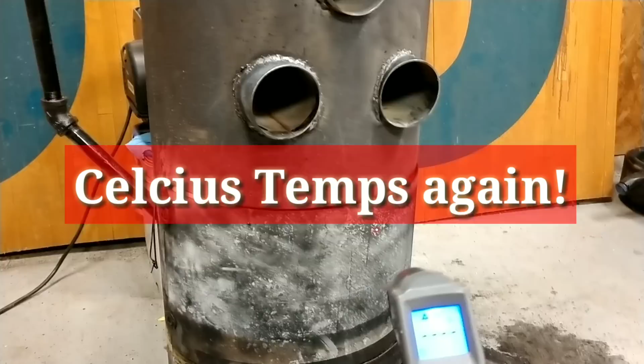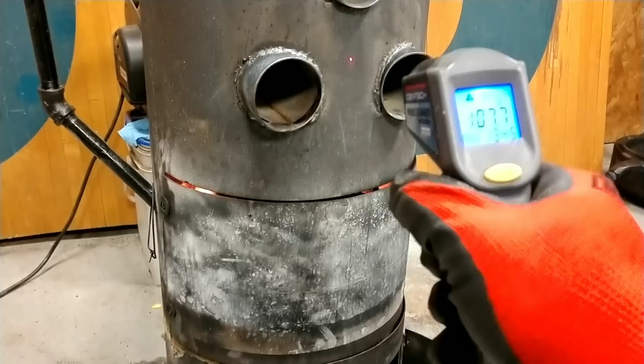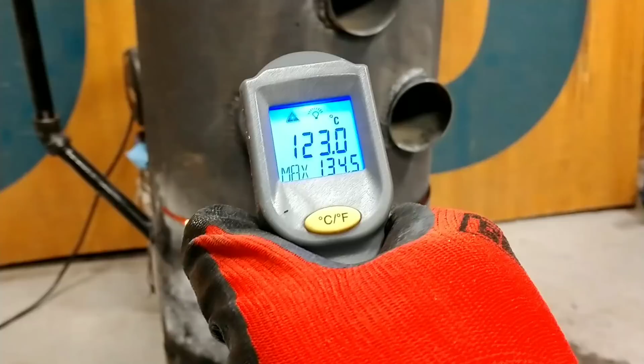And let's check some temperatures. It's been a couple of minutes now. The door is up to 130. The tank where the heat exchangers are, I can't really see too much with the glare on the lens there. 122, 123. There we go, 123. We're still getting hotter inside. 128. So we're still looking at a stream about the size of a pencil lead, and you can hear the roar of the tank.